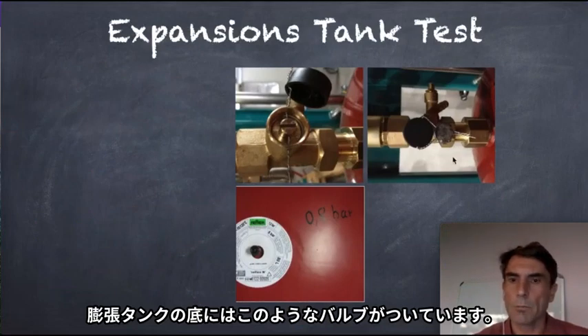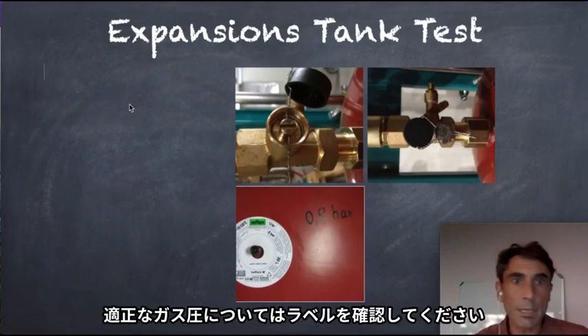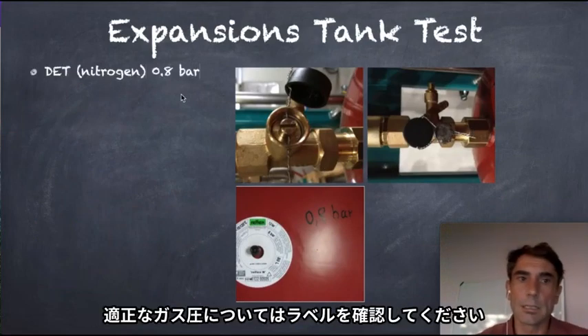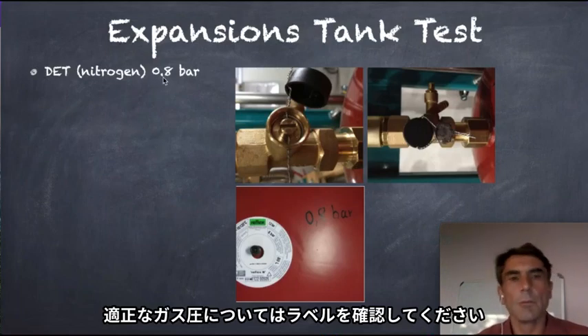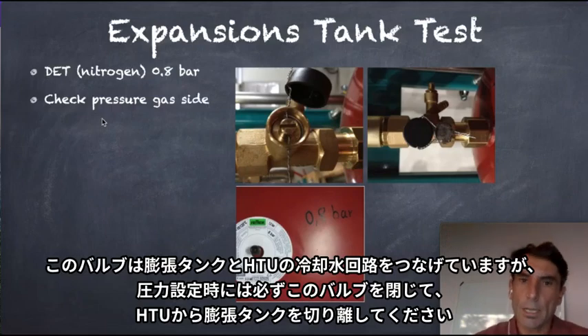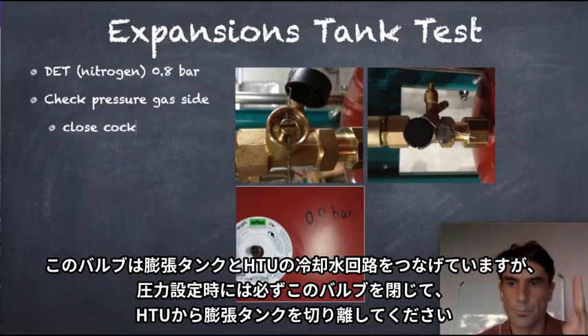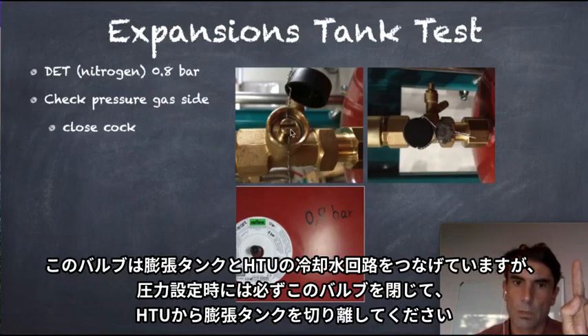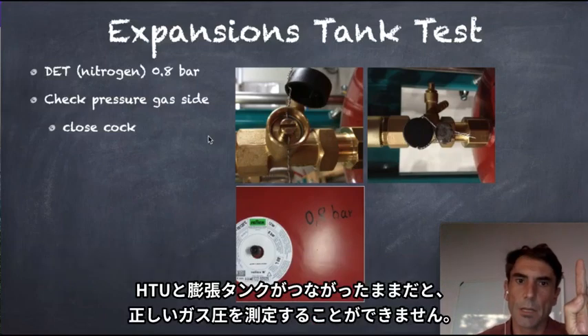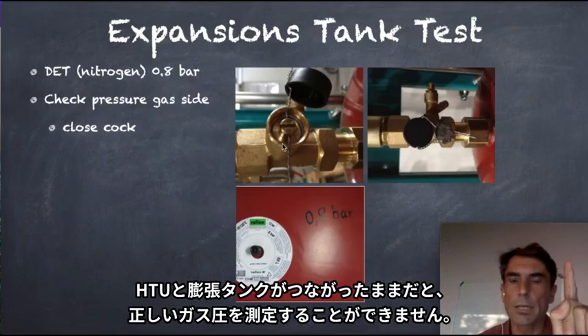Here on the bottom of the expansion tank, it doesn't matter which one, this is the expansion tank for the HTU with 0.8 bar as gas filling pressure. Then we can check the gas side. If we would like to check the gas side of the expansion tank, first we have to close that cock. That cock connects the expansion tank from the water side to the HTU water side. If the water side stays connected, we cannot measure the gas side properly because we still have the water pressure on that side that will change the gas pressure on the other side.